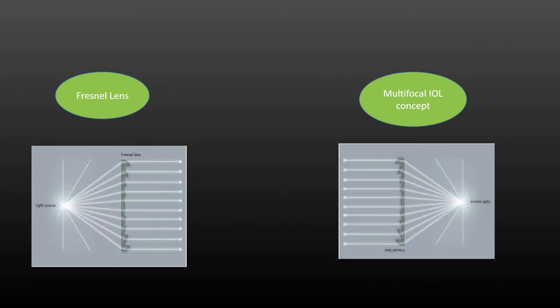The concept of today's multifocal IOL has its genesis in Fresnel lenses. The Fresnel lens collected light from the lamp and the sawtooth pattern made it parallel. In the multifocal IOL it is just the opposite, but the concept remains the same — here we collect parallel light and bring it to focus. The function differs: in Fresnel lighthouse lenses they collect light and make it parallel; here we collect parallel light and make it converge into a focal point.